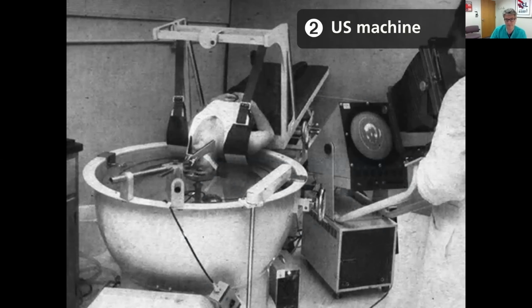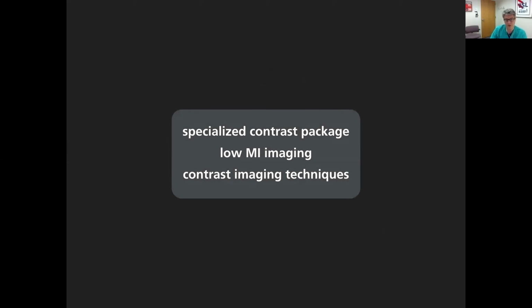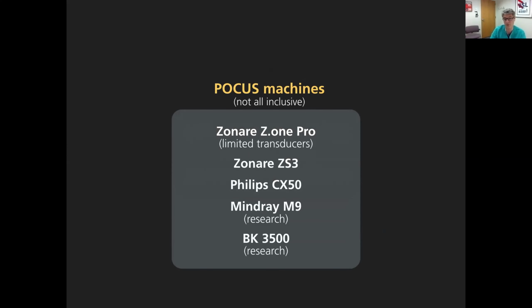So what about the machine? The ultrasound machine needs a specialized contrast package on it, which mainly is low MI imaging, and then it needs these specific contrast imaging techniques. The next slide shows some machines, and this is definitely not an endorsement of any manufacturer. These are the ones that I know can do contrast imaging at the point of care. I asked the different manufacturers about a year ago. This is really not inclusive, and there might be other ones where you can scan on battery with the contrast, but these are the ones that I know you can scan on battery at the bedside.